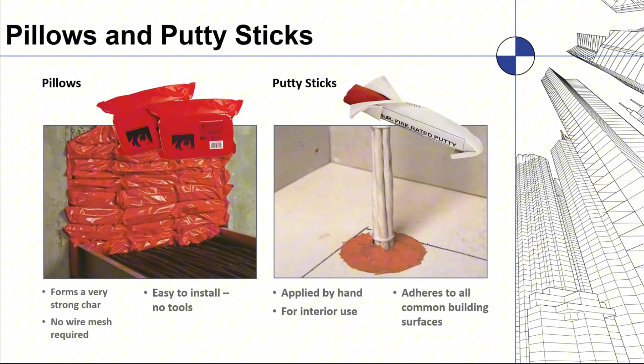You can have very large openings to fill in construction for fire stopping. This is really common in cable trays, where pillow applications take place. People like pillows because they're removable - if you increase the size or add more cables to your cable tray, you can pull out a pillow, or add one if it's taken down, modifying it once it's in place.